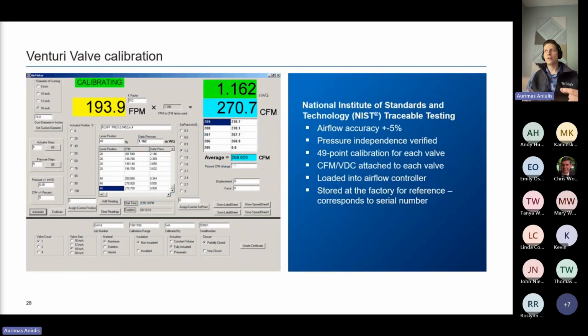That calibration is done at our factory in Norcross on a NIST traceable setup, which has plus or minus 5% accuracy. It verifies pressure independence, and does a 49-point calibration for each air valve. That same CFM to volt data is attached to each valve. It's loaded in its brain, and it's stored at the factory in case there's some event in the field where you need to replace the curves for the device.